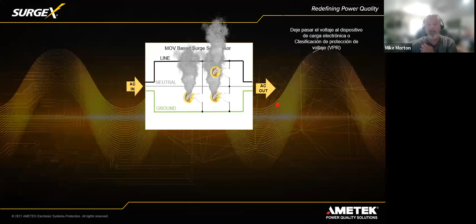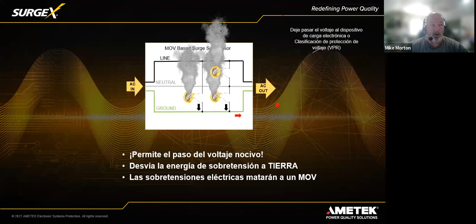Unfortunately, the way this works is, since it is not very accurate, this actually has a problem. Typically, one of the MOVs will blow and will leave one of the legs of the circuit open to any kind of anomalies that might happen. So anything that would be on that circuit would now be susceptible to those types of power anomalies, and therefore can cause damage to your products.